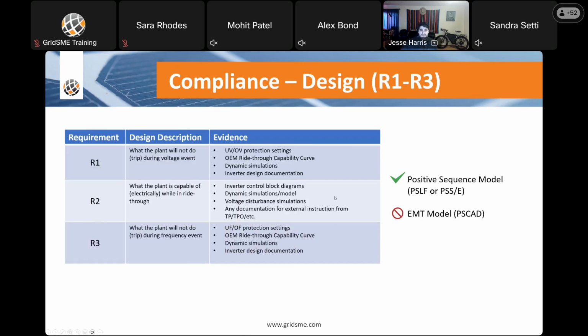So what sort of evidence do you need in order to show compliance? Requirement R1, remember, it's just saying what the plant will not do. It's not going to trip during a voltage event. The evidence for this could be under voltage, over voltage protection settings, OEM ride-through capability curves, dynamic simulations, inverter design documentation. R3 is very similar to that. What the plant will not do, will not trip during a frequency event. So all the evidence is the same, except instead of under voltage and over voltage protection settings, you'll have under frequency and over frequency protection settings.